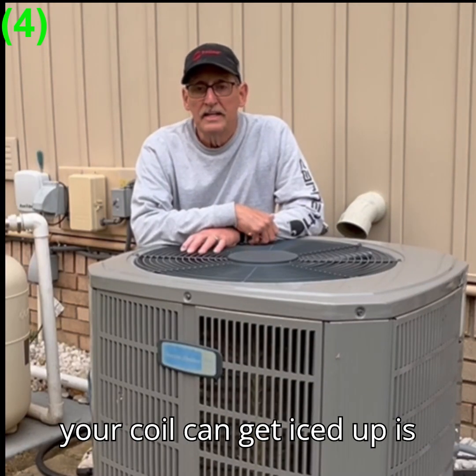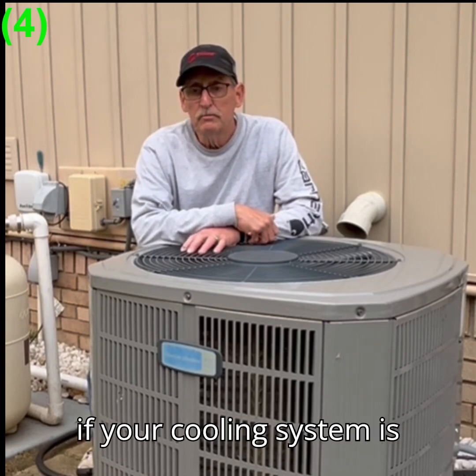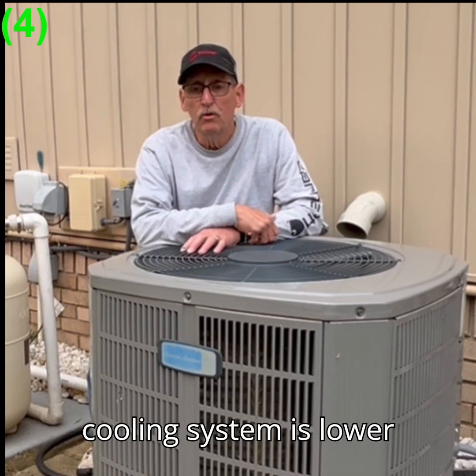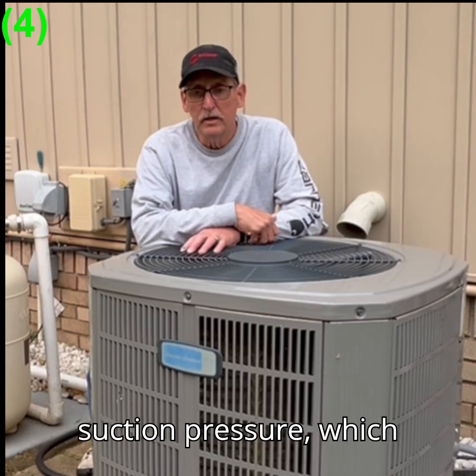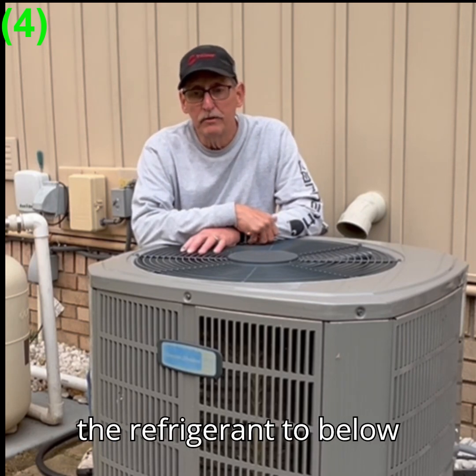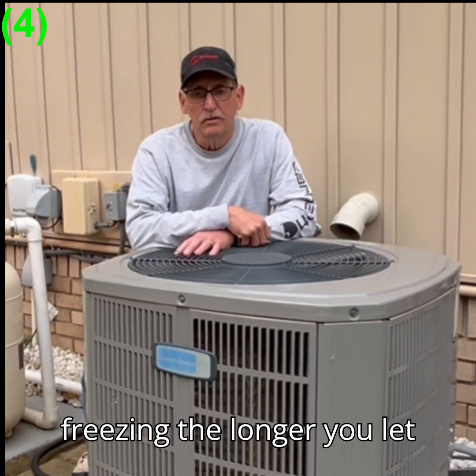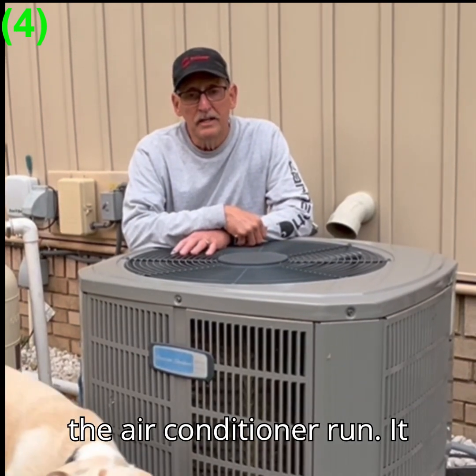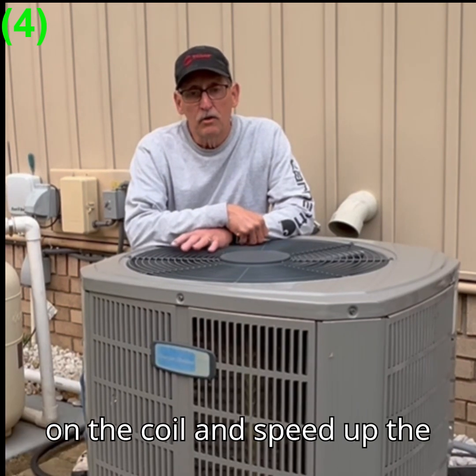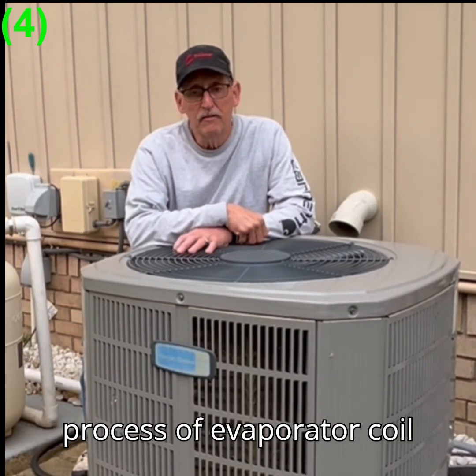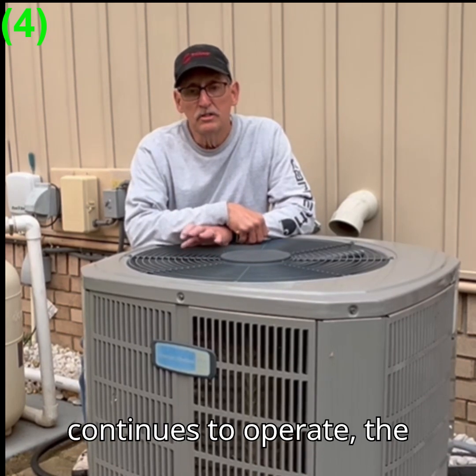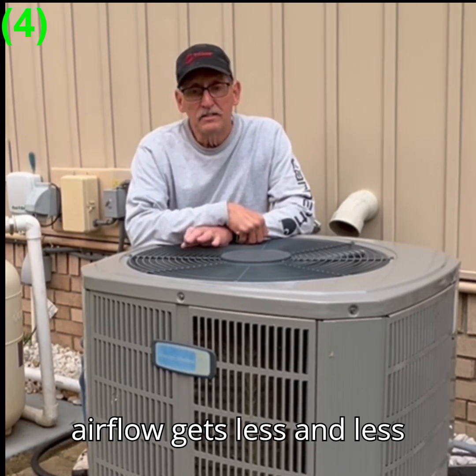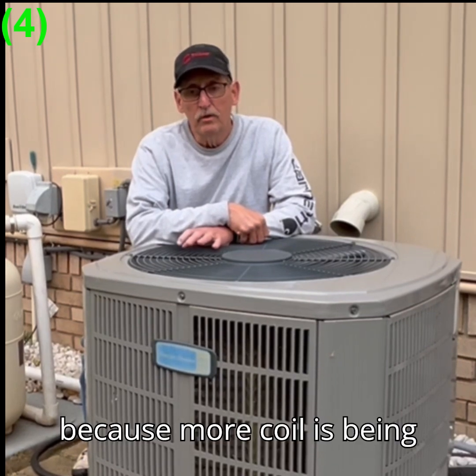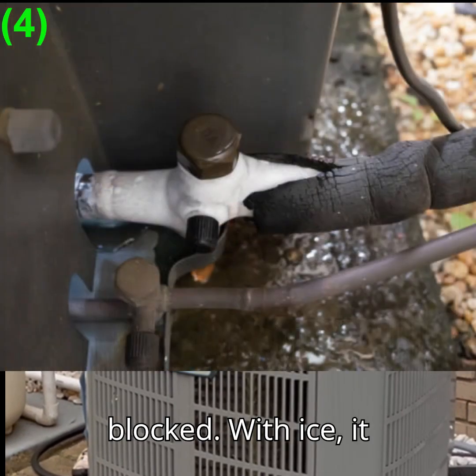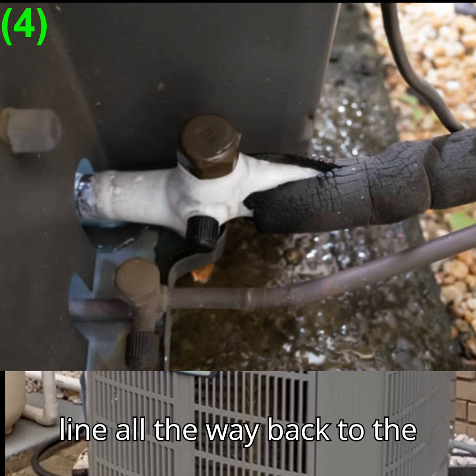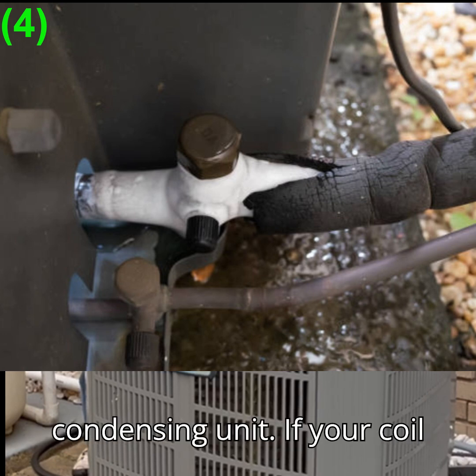Another reason your coil can get iced up is if your cooling system is low of refrigerant. When your cooling system is low of refrigerant, it lowers the suction pressure, which lowers the boiling point of the refrigerant to below freezing. The longer you let the air conditioner run, the more ice accumulates on the coil, which speeds up the process of evaporator coil freezing. As the system continues to operate, the airflow gets less and less because more coil is being blocked. With ice, it sometimes freezes the suction line all the way back to the compressor outside in the condensing unit.